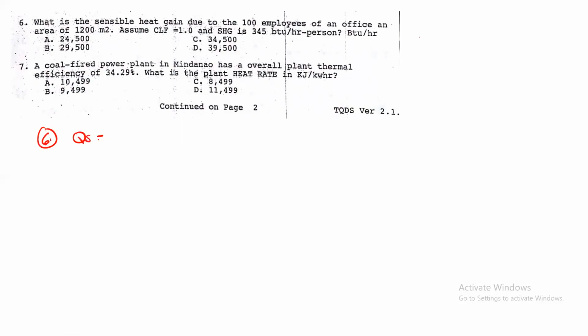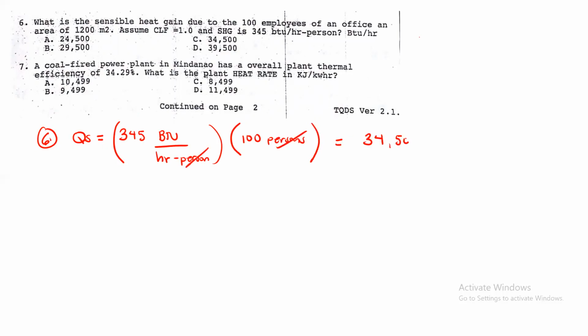So QS is equals to, so ilan ba yung given? So SHG 345 BTU per hour per person. So ito times mo lang yan ng 100 persons or 100 employees. So syempre unit analysis lang, makukuha mo na yung BTU per hour. So 345 times 100 is 34,500 BTU per hour. So ganyan lang siya, guys. So hindi mo na kailangan mag-isip ng kahit ano pang formula. So kahit hindi mo na alam yung ibig sabihin ng CLF at saka SHG. So halata namang sa unit pa lang ng choices, makukuha na natin yung sagot.